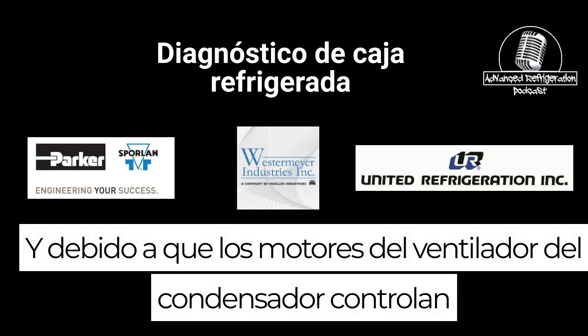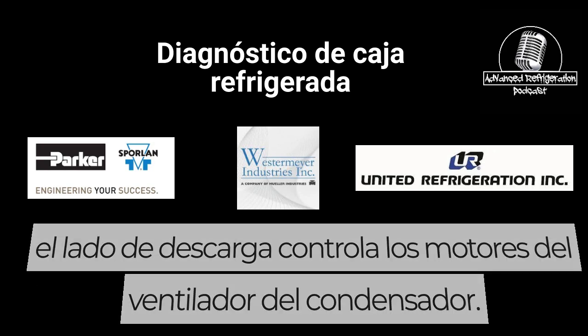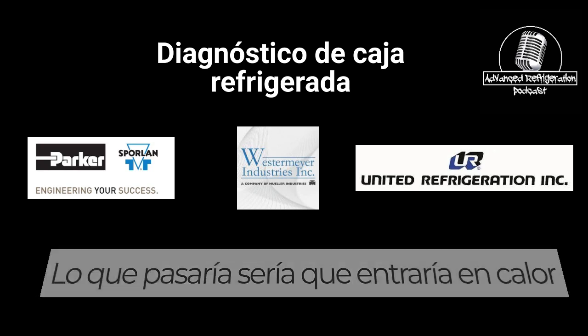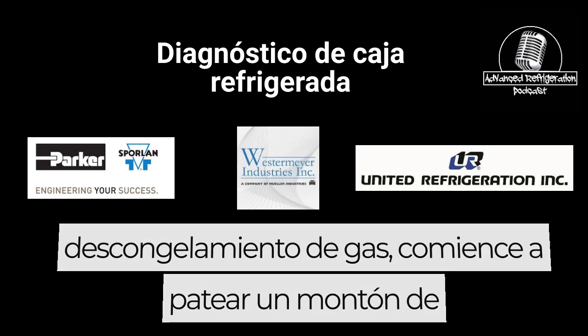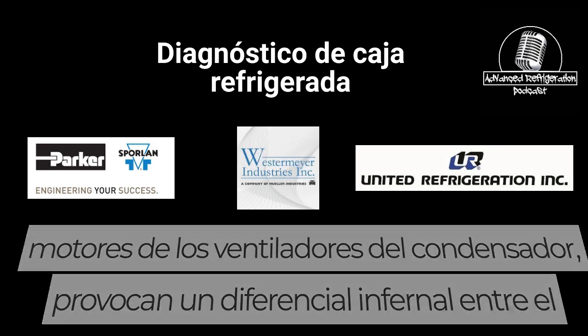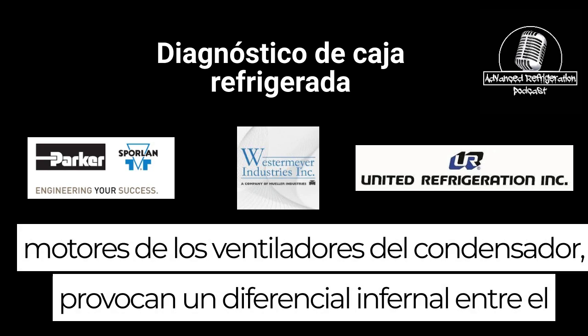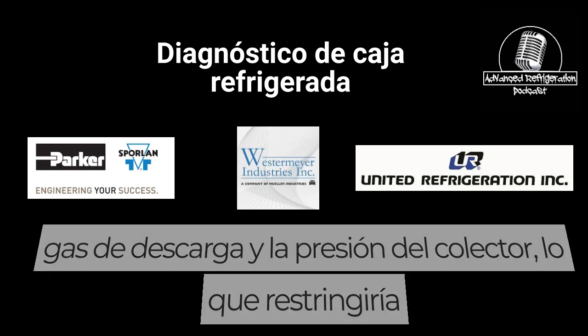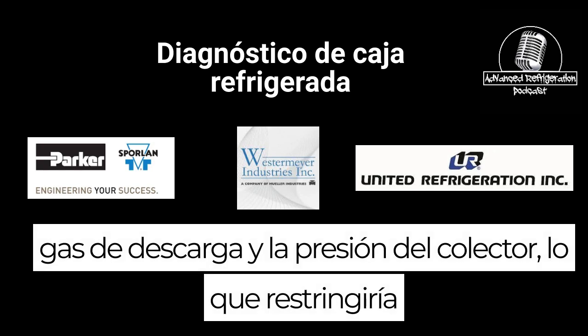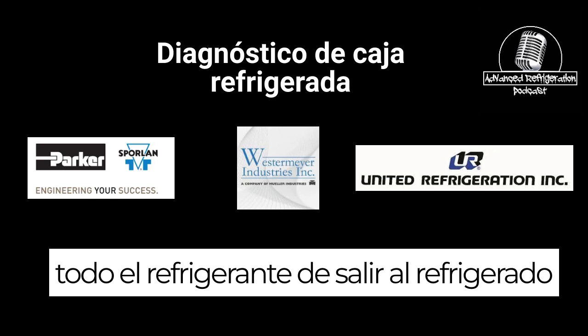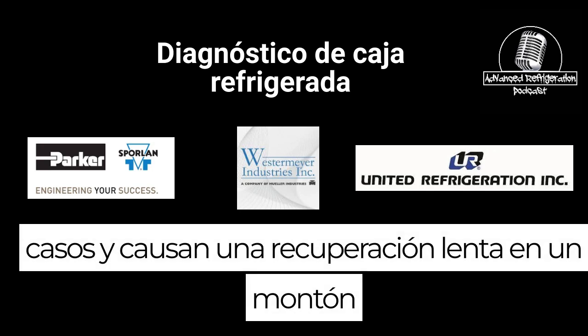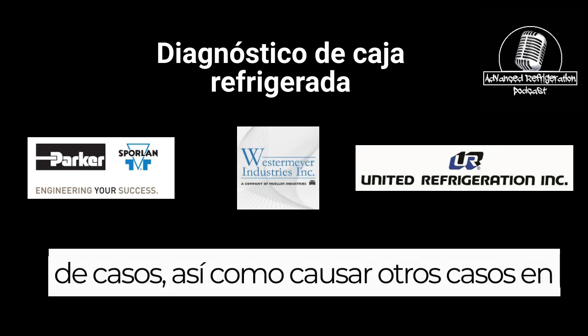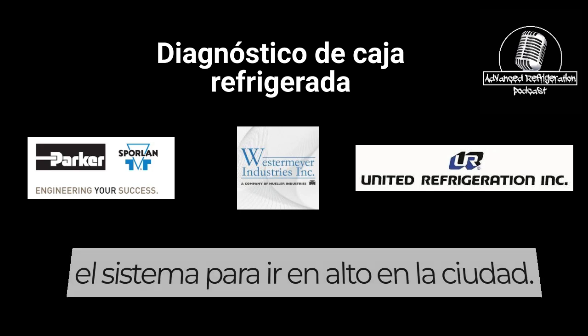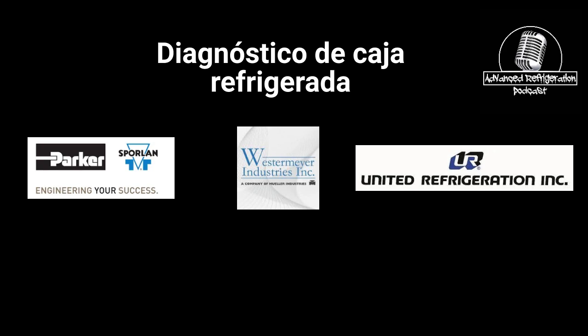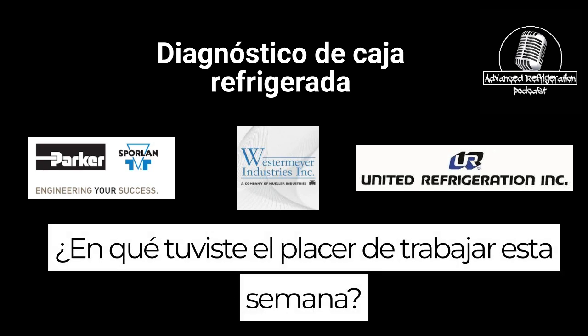And because the pressure transducer on the discharge side controlled the condenser fan motors, what would happen was it would go into hot gas defrost, start kicking on a whole bunch of condenser fan motors, cause a hellacious differential between the discharge gas and the header pressure, which would restrict all the refrigerant from going out to the refrigerated cases and cause slow recovery in a whole bunch of cases, as well as causing other cases on the system to go in high and down. What did you have the pleasure of working on this week, Kev?